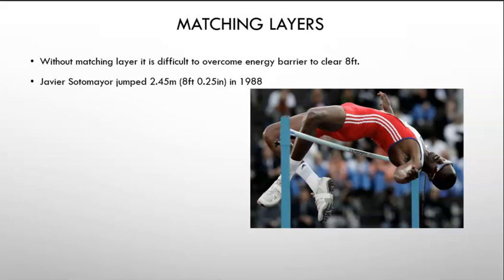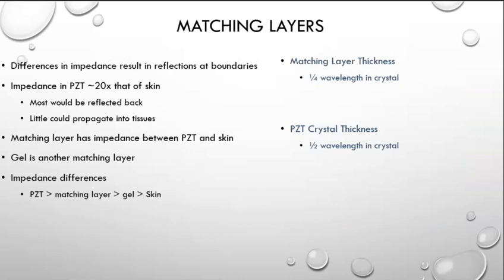Now, the matching layer, if you think about that huge impedance difference between the body and the crystal, the matching layer is going to help us overcome that 8-foot barrier. And I'll go into how that works. So the impedance of the piezoelectric material, the PZT, is about 20 times that of the human skin. So most would be reflected back, and very little would be transmitted into the tissues for imaging purposes. And then once it went into the tissues and the echoes came back, most of those echoes would be reflected back into the tissues, and we'd get very little back to the transducer at that point.